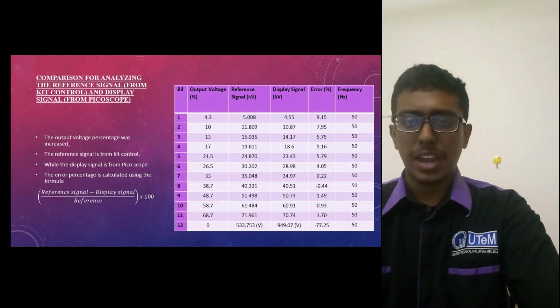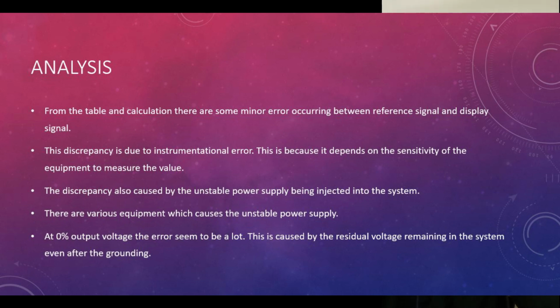Okay, for the analysis, from the table and calculation, there are some minor errors occurring between the reference signal and display signal. This discrepancy is due to instrumentational error, because it depends on the sensitivity of the equipment to measure the value. The discrepancy is also caused by the unstable power supply being injected into the system. There are various equipment which cause the unstable power supply. At 0% output voltage, the error seems to be large. This is caused by the residual voltage remaining in the system even after grounding. Manual discharge is required for it to be operated safely.